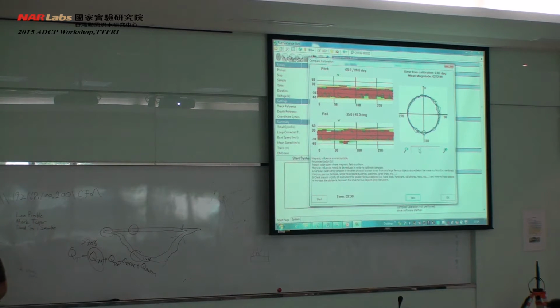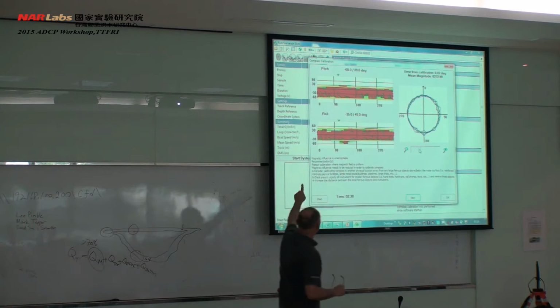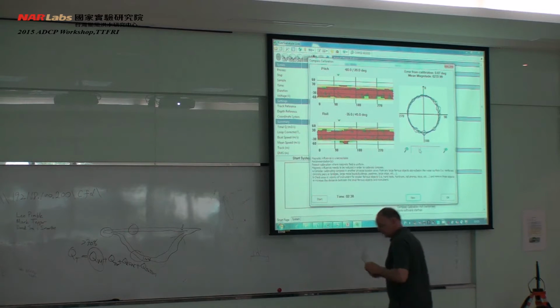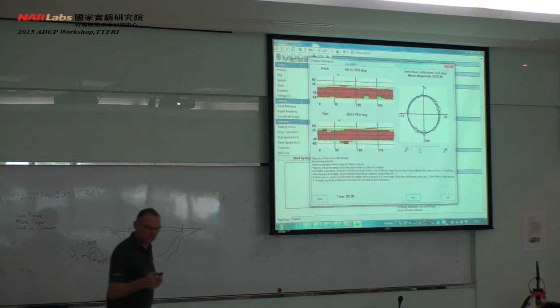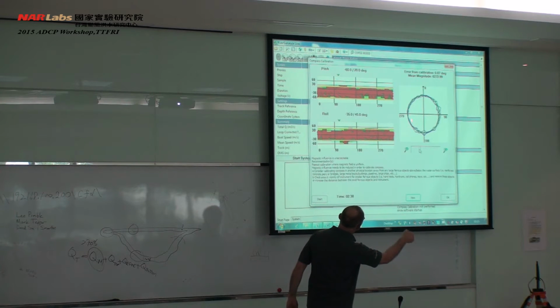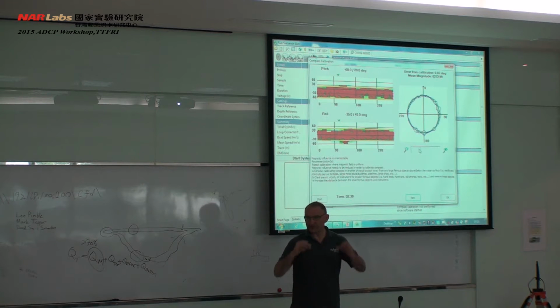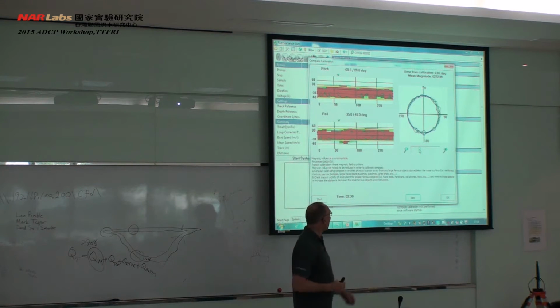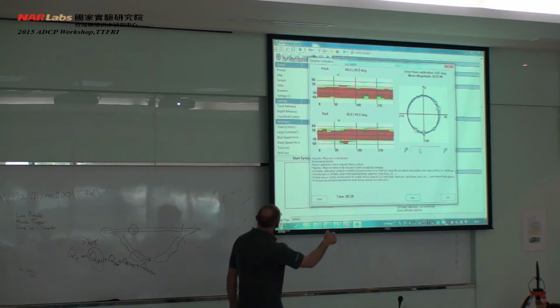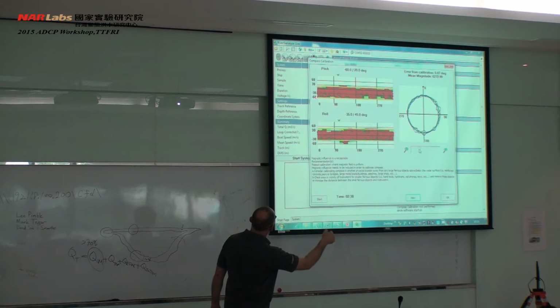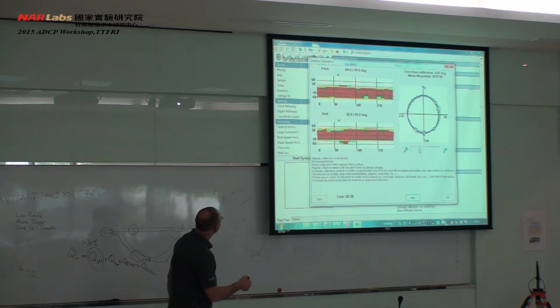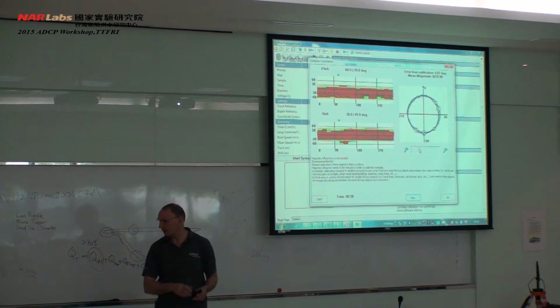My question is, if the calibration is okay, what does the figure show? So it says it has passed. And where we see here, this is pretty good. That will be the same all the way round. You'll see a nice tight circle all the way round. And then on here, this is saying what our calibration limits are on the pitch and the roll. That's around 40 degrees, positive and negative, on the roll, and 20 on the pitch. So Mark had a bit of a bias in the way he was holding the instrument for the pitch.